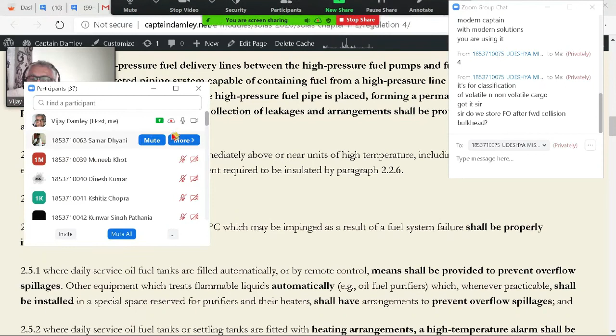Fuel pipelines you will not locate immediately above or near high temperatures, like the exhaust, because when an engine is using energy, they can't use 100%. Most of these internal combustion engines go between 30 and 40% efficiency in terms of energy. So exhaust gas temperatures are 400 degrees. That is why you make sure that fuel oil lines will not be close to any of the heated places.